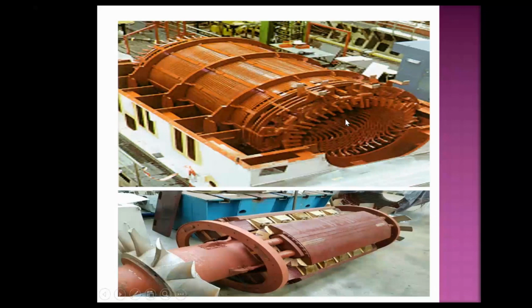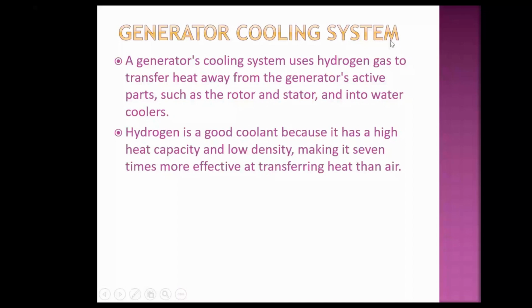After receiving the energy from this part, the hydrogen temperature will also increase. So that heat is removed with the help of a water cooler. So the purpose of hydrogen in a thermal power plant is basically for cooling the generator. The generator cooling system uses hydrogen gas to transfer heat from the generator parts, such as rotor and stator, into the water cooler. Hydrogen is a good coolant because it has a high heat capacity and low density, making it 7 times more effective at transferring heat than air. It is 7 times more effective than air.